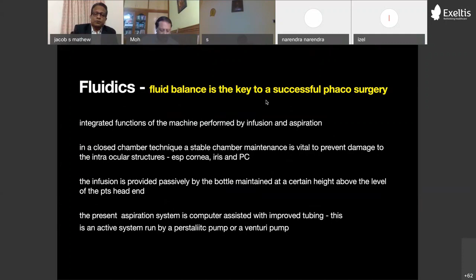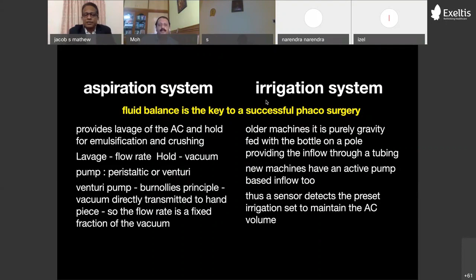Whereas the Venturi pump works on Bernoulli's principle, where a high pressure gas is passed through a tube, and the negative pressure that is created thus is directly passed on to the tip of the phaco probe. So there is a higher kind of vacuum that is directly transmitted to the phaco handpiece, and the flow rate is fixed in the Venturi pump. So these are the points that I think I have already mentioned. So I will go to the next slide.